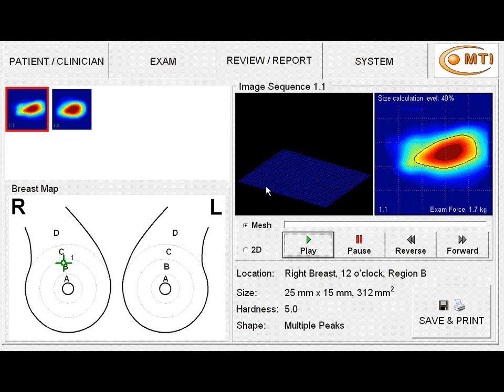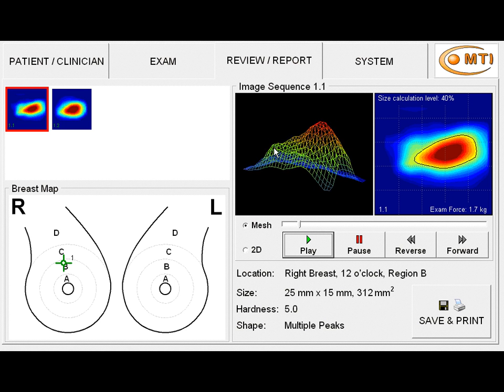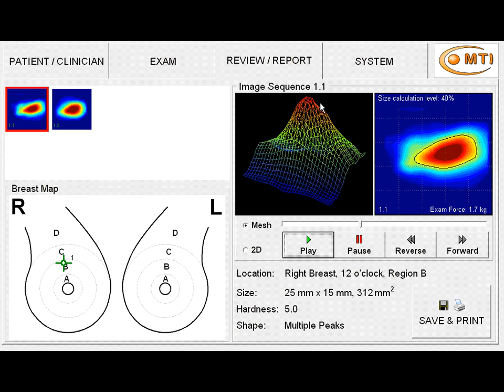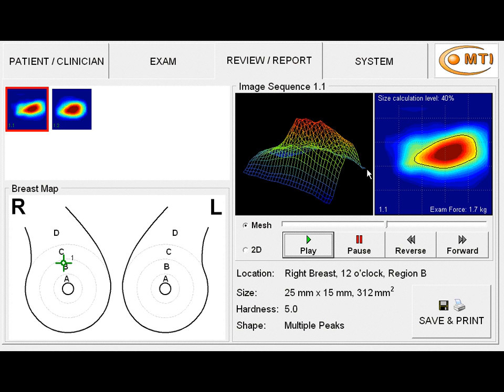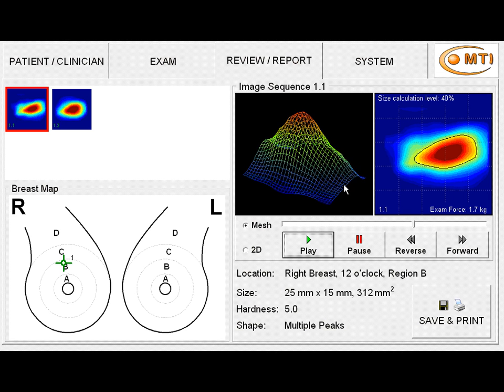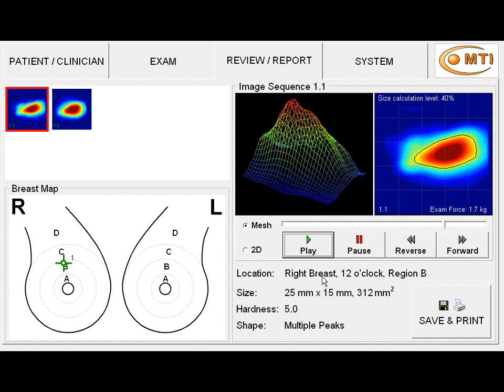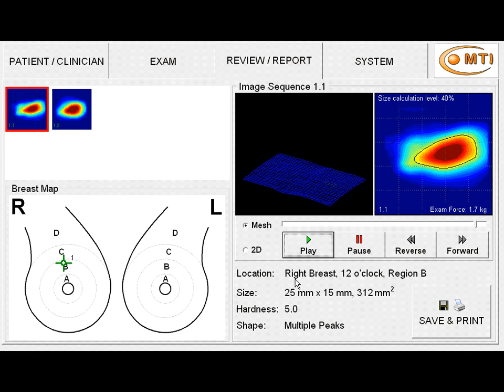If the mass was as big as the whole transducer, then we wouldn't have any 0 point, and the whole level of the mesh would rise, and we wouldn't have a 5. We might have 0 hardness if the entire mass filled the entire transducer. But in this case it doesn't, and we see a big peak here with multiple shoulders. And as we move it around, we see several multiple peaks. And this certainly is a very suspicious mass. It's on the right breast at 12 o'clock, measuring 2.5 centimeters by 1.5 centimeters, and quite hard and multiple peaks.